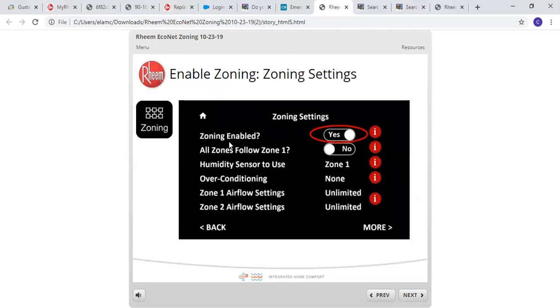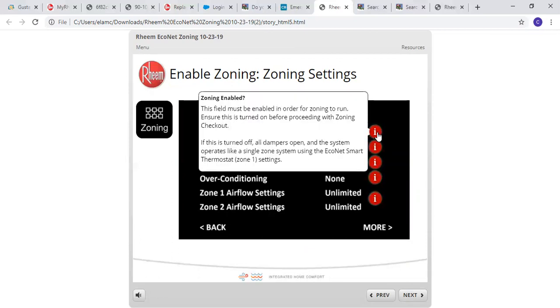So if you want to enable the zoning, you would highlight this and turn that on. This field must be enabled in order for zoning to run. Ensure this is turned on before proceeding with zoning checkout. If this is turned off, all dampers are open and the system operates like a single zone system.